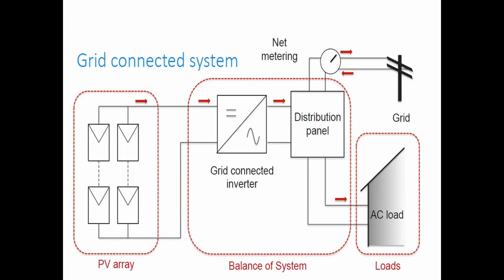But the problem with the grid-connected system is that when the supply is turned off, our PV plant will also turn off. This is required, and we call it anti-islanding. In an anti-islanding system, when the KSEB supply or grid is turned off, our power plant should be isolated.